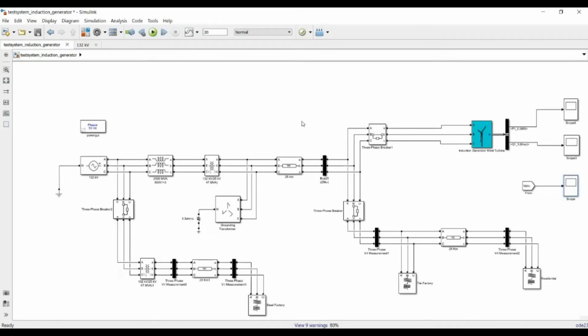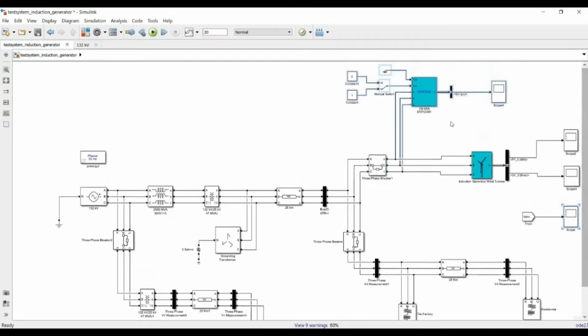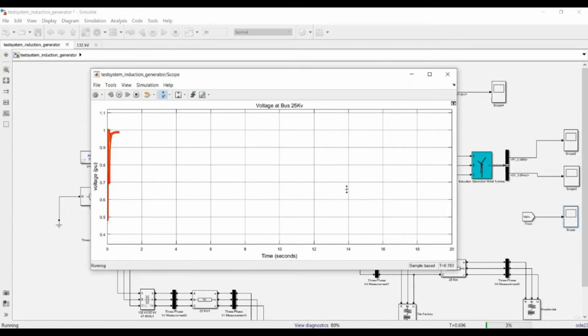So I am applying a reactive power compensator, which is a STATCOM, static compensator. So this is my STATCOM. After applying the compensator, the per unit voltage at the 25 kV bus has been improved, there is no more transient response, and the per unit voltage is at level 1.